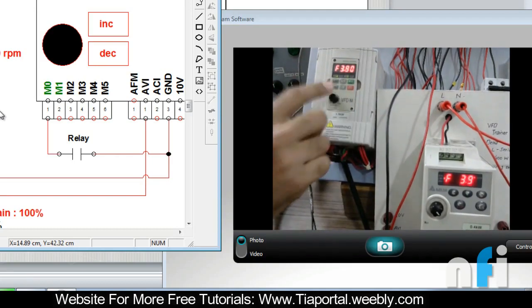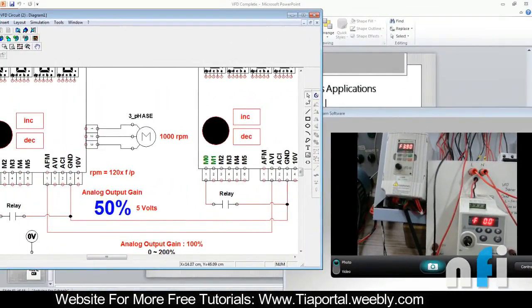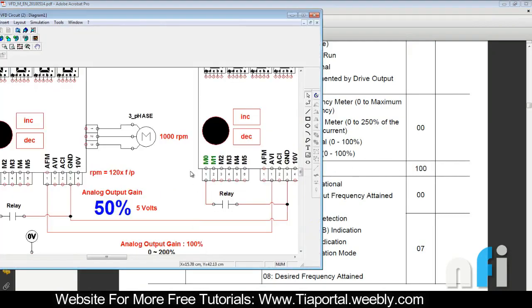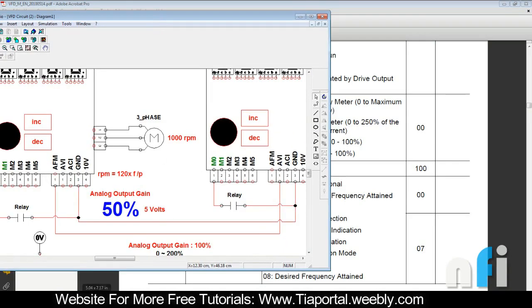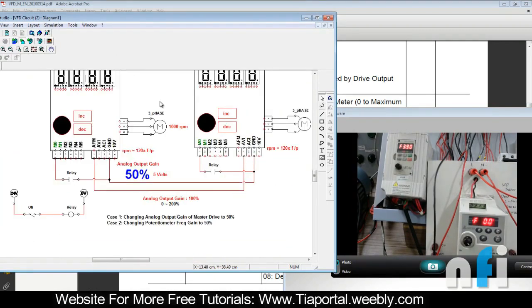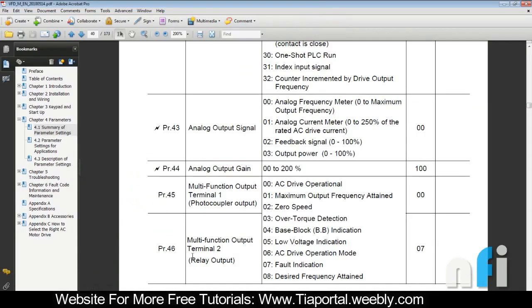At a one-to-one ratio, if I increase to 4.6 Hz it will be 4.6 Hz on the slave. You can also play with the gain. There is a parameter associated with the analog output gain, which by default is 100%. If you change the gain to 50%, your frequency settings will be in a 2-to-1 ratio — if the master is at 50 Hz, the slave will be at 25 Hz.